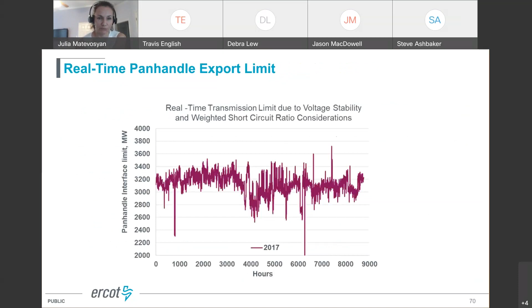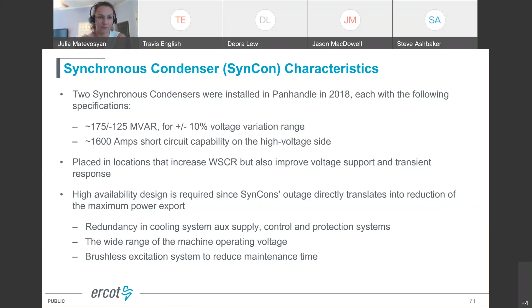As I mentioned, 2 synchronous condensers were installed in 2018 to improve system strength in the Texas Panhandle. There are 2 175 megavar condensers. They were placed in locations where they could increase weighted short circuit ratio, but also they were optimized to provide voltage support and transient response. So location was chosen not only on short circuit ratio considerations. The design that we went for was to have high availability and reduce maintenance, because its impact on export out of Panhandle is very big and has economic impacts on plants in this area.